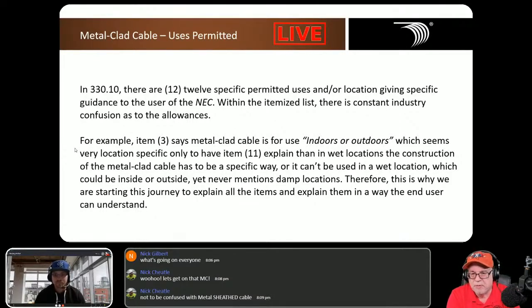Typical MC is not rated for a wet location. It might have wet location rated conductors inside it, but typically it's a dry location rated product, for use in dry applications. However, there are certain things we can do to that MC to create its use in a wet location.